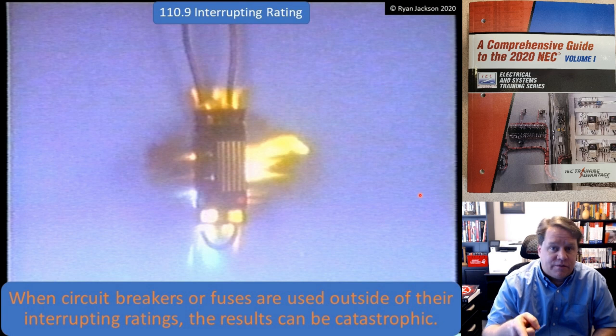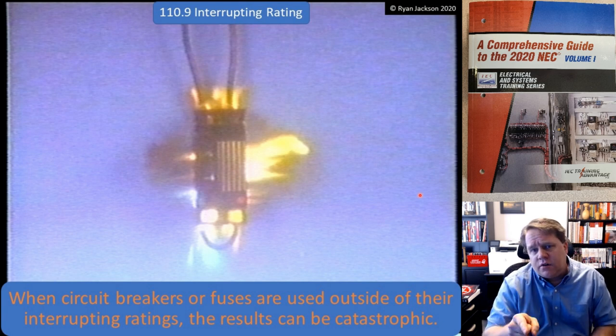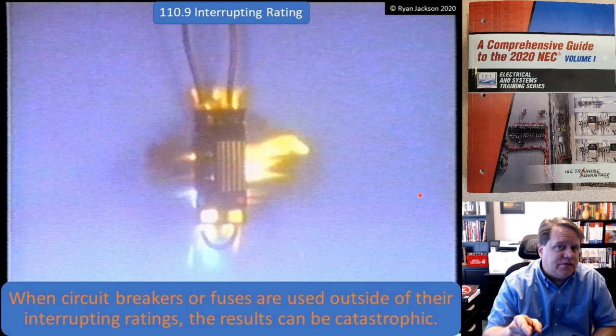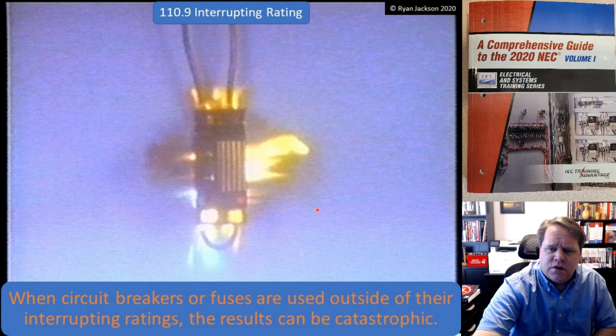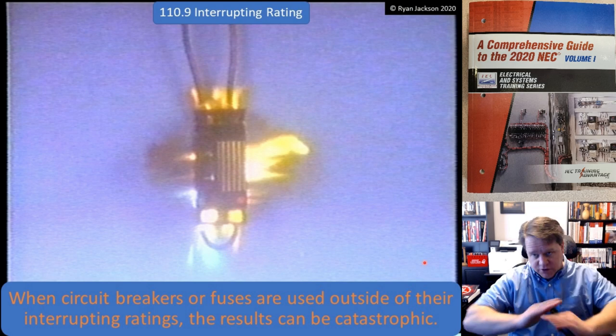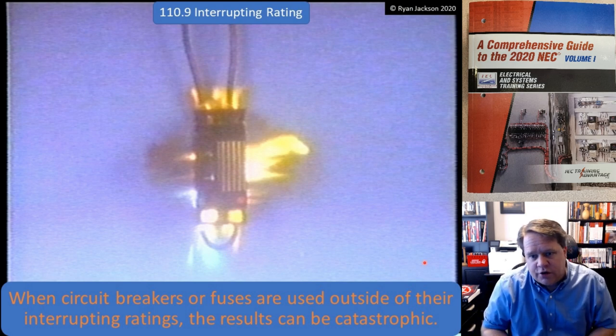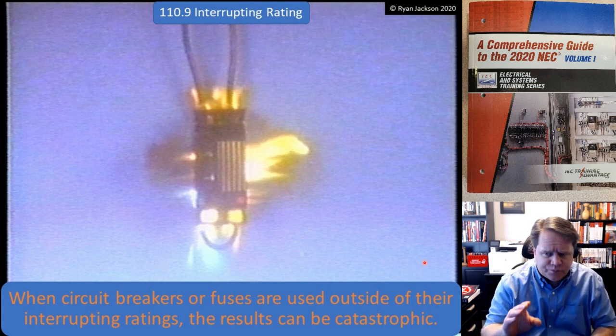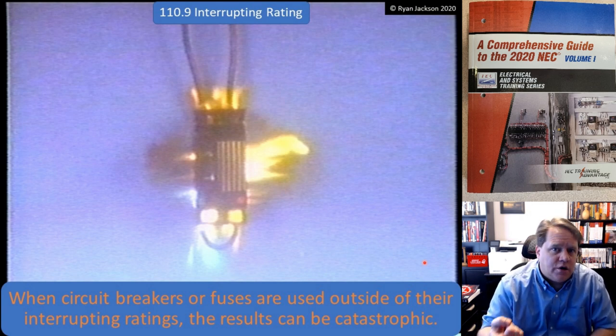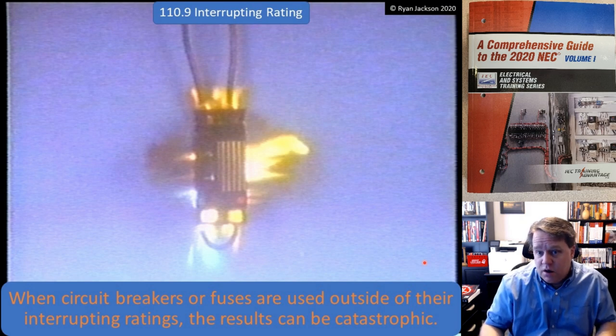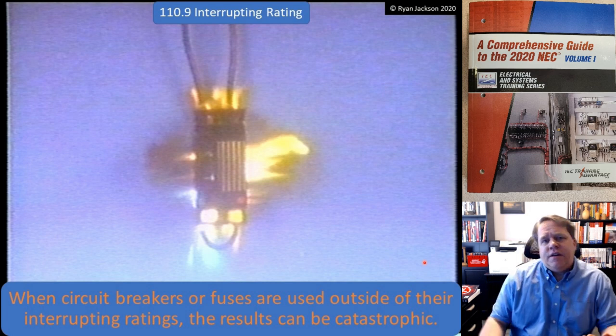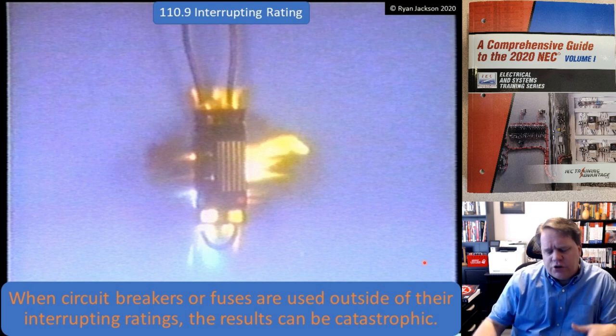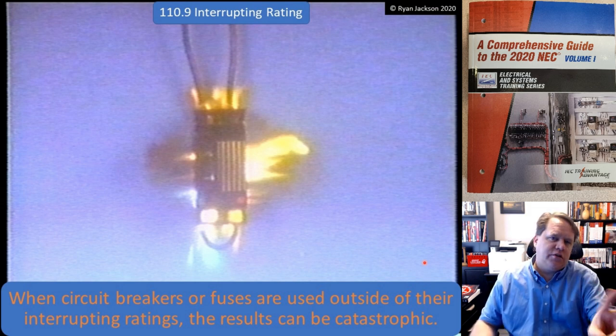This is a circuit breaker rated 14,000 amps being subjected to 50,000 amps. They've jumpered the load side of the breaker line to line - a direct 480-volt short circuit. That's rated 14,000 amps with 50,000 amps across it. That's a gross misapplication and we've got fire and everything else shooting out of the circuit breaker. But if you really think about it - do you check the interrupting ratings when you're replacing circuit breakers?